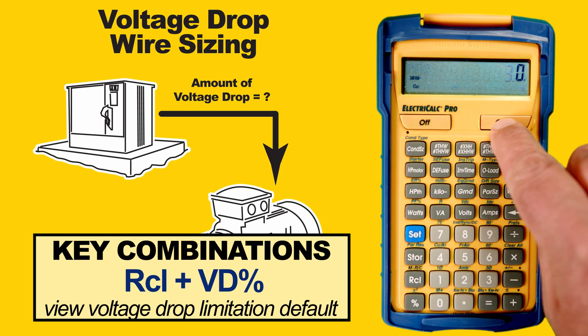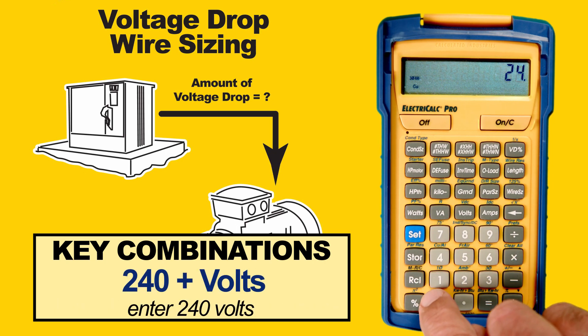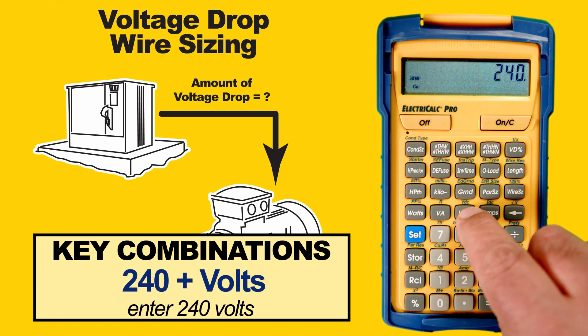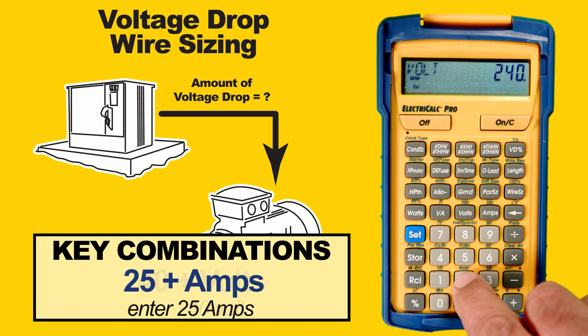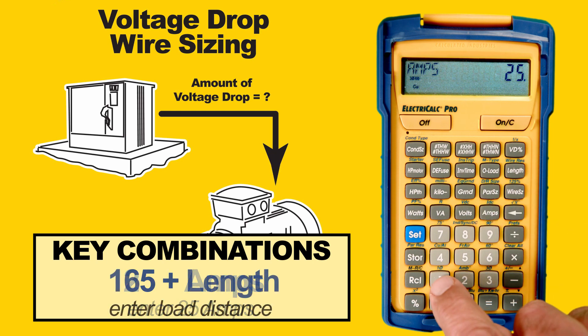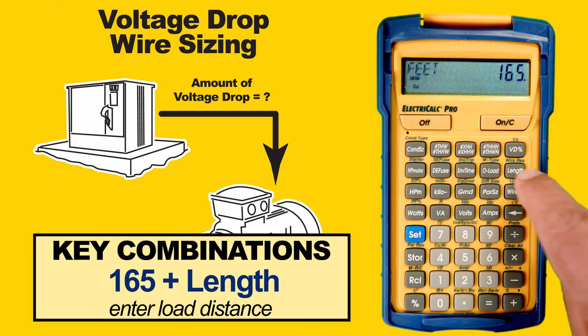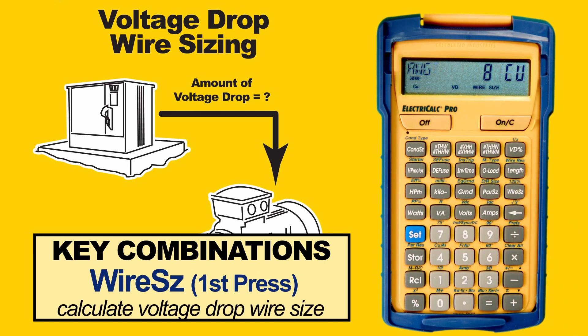Now we enter our volts. In our example, we have 240 volts, so we key 240 and then press Volts. We have 25 amps, so we key 25 and press the Amps button. Our load is 165 feet away, so we enter that and press the Length button. We press Wire Size and it says that we will need a number 8 voltage drop wire size.